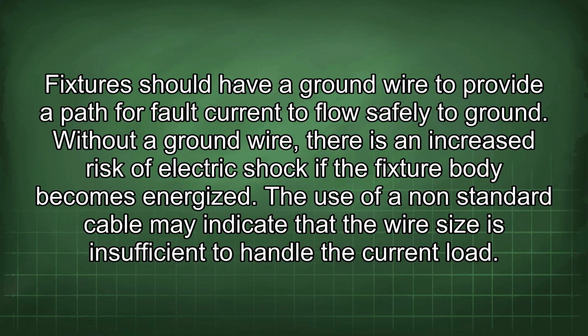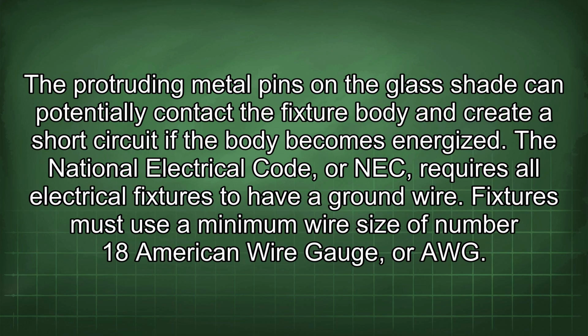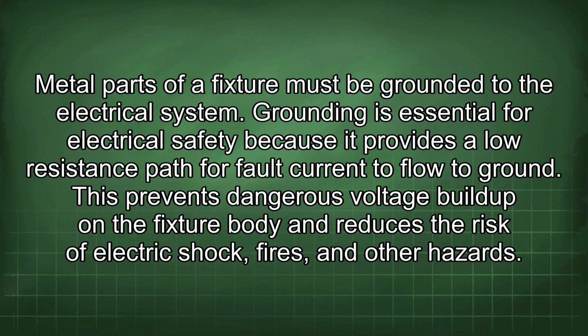The use of a non-standard cable may indicate that the wire size is insufficient to handle the current load. The protruding metal pins on the glass shade can potentially contact the fixture body and create a short circuit if the body becomes energized. The National Electrical Code, or NEC, requires all electrical fixtures to have a ground wire. Fixtures must use a minimum wire size of number 18 American wire gauge, or AWG. Metal parts of a fixture must be grounded to the electrical system.